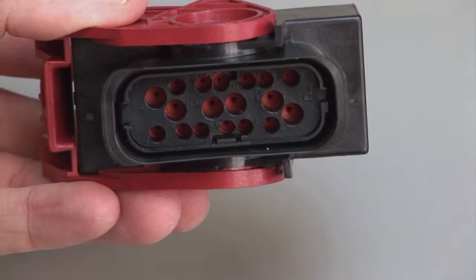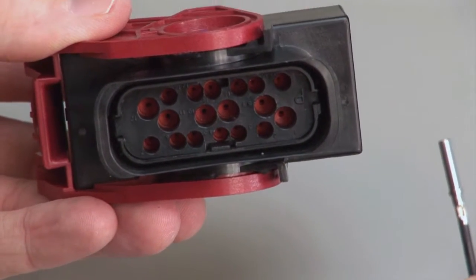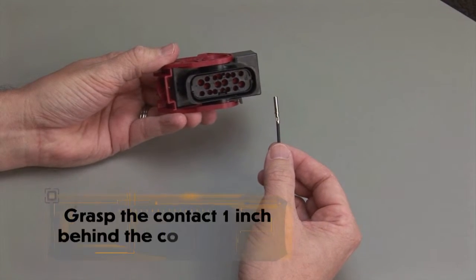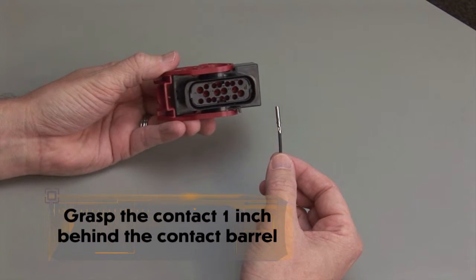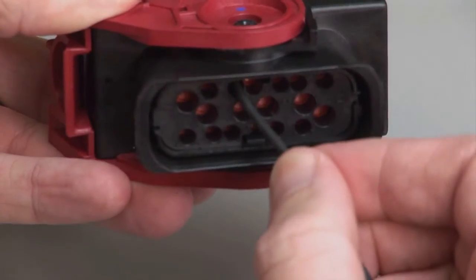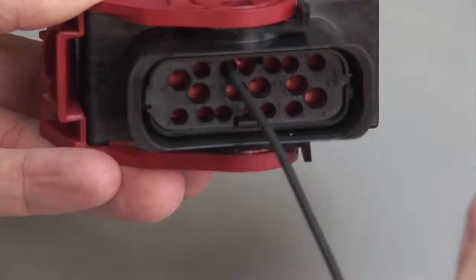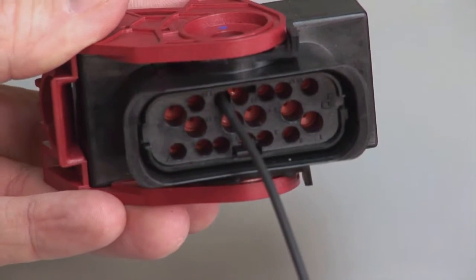Hold the connector with the rear grommet or wire router facing you. Grasp the crimped contact approximately one inch behind the contact barrel. Push the contact straight into the rear grommet or wire router until you hear and feel a click. A slight tug will confirm that the contact is properly locked into place.